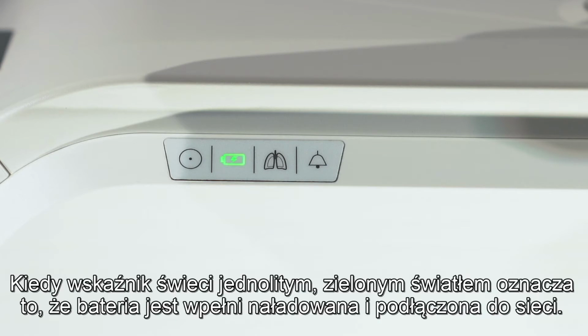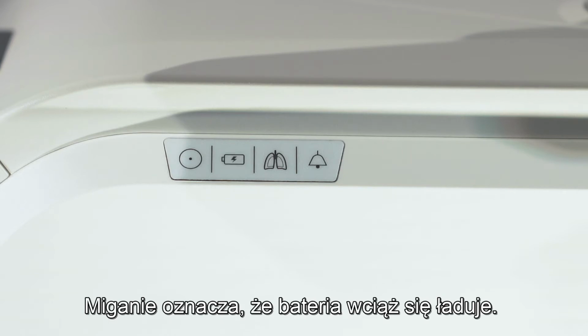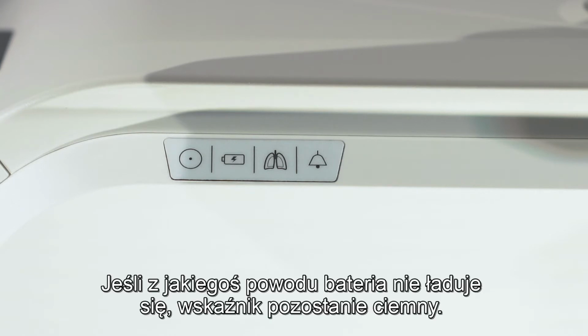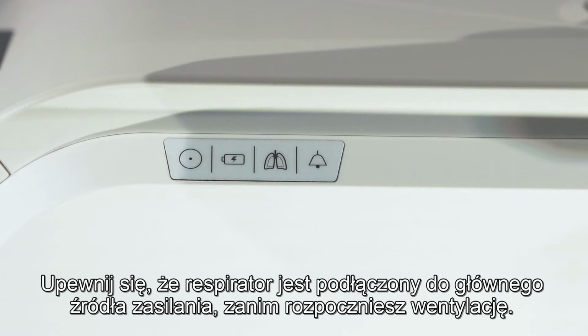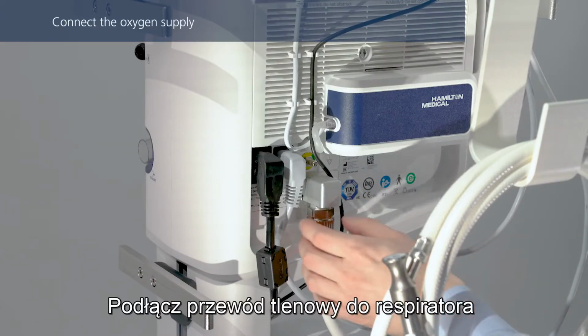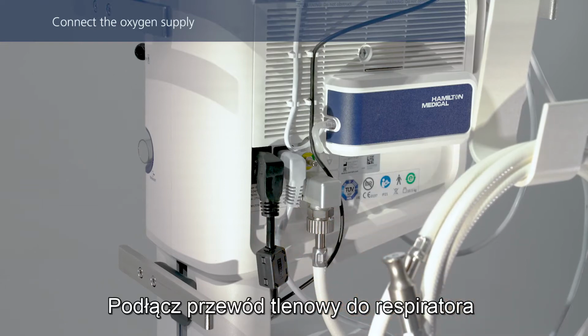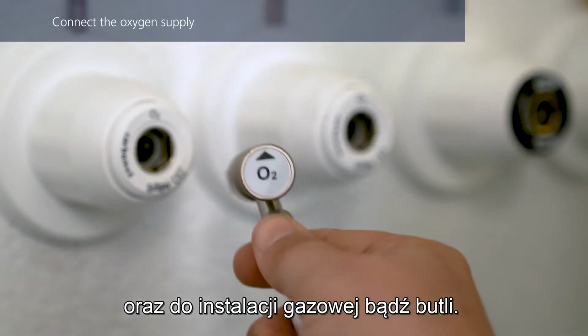turned off. When the indicator is solid green, the battery is fully charged and connected to primary power. When flashing, it means that the battery is still charging. If the battery is not charging, for whatever reason, the indicator will remain dark. Make sure the ventilator is connected to a power source prior to starting ventilation. If you haven't done so already, connect the oxygen hose to the ventilator, and then to the gas supply or a gas cylinder.